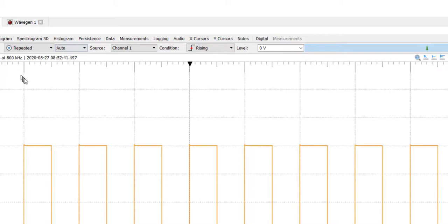And so it's constantly going to that buffer. And while it's going in, the trigger circuit is looking at that input voltage. If that voltage goes above the level we set with a rising edge, then we're going to immediately display, at that instant of time when we get that condition, that waveform. And that's what we're doing right now.